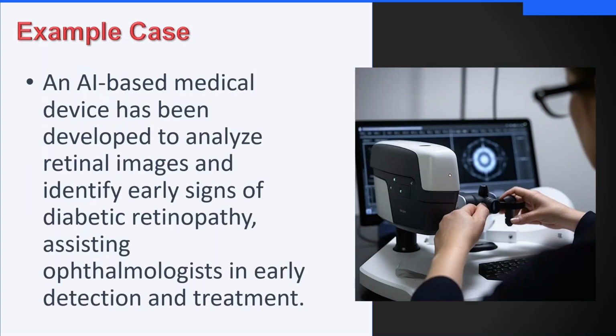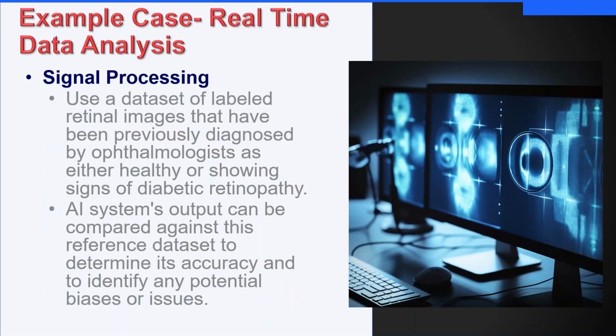So another example, or using the same example, but another case just focused on monitoring. So we have our diabetic retinopathy device again, and this time they use real-time data analysis. They took a set of data that was already labeled and curated by ophthalmologists and basically used that as a reference standard and would compare the device's performance over time against that reference data set to make sure that it was still performing, that you weren't seeing drift, and that the algorithm, this is particularly if the algorithm is not locked, that it's not trying to like retrain itself.